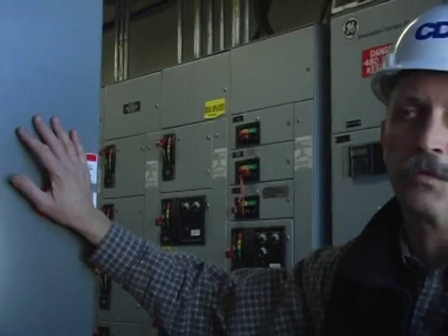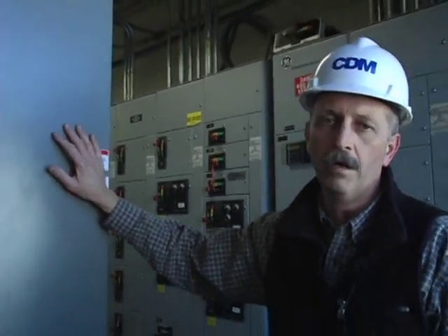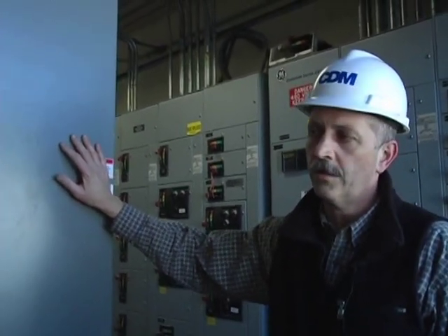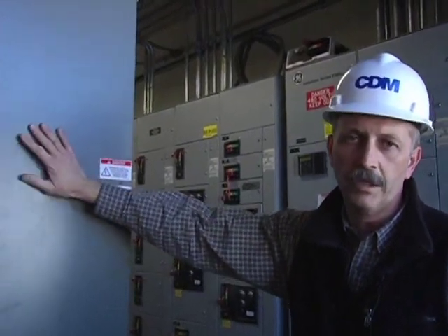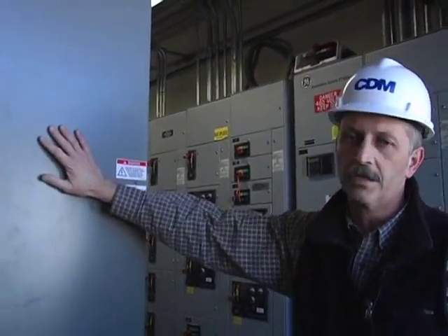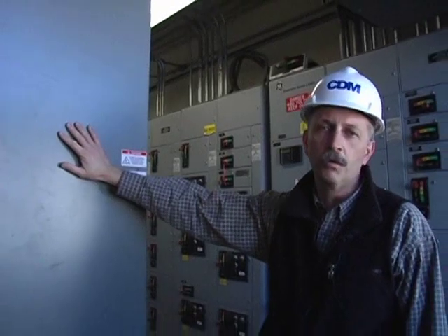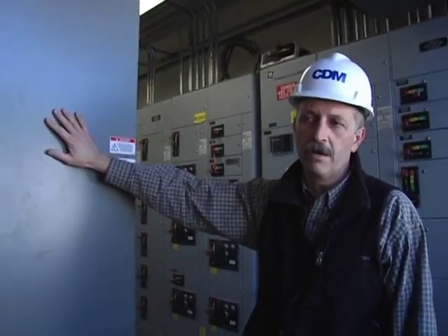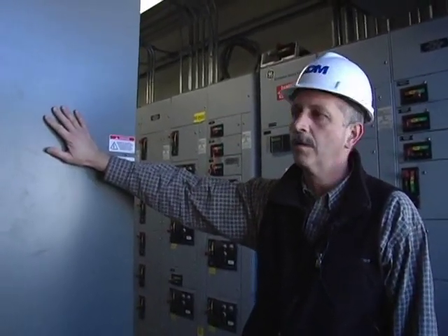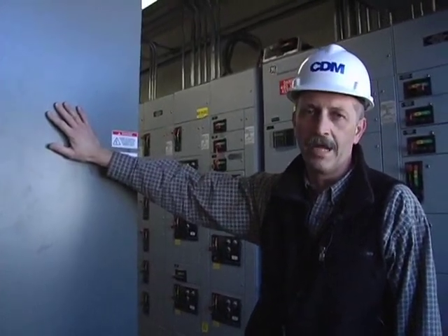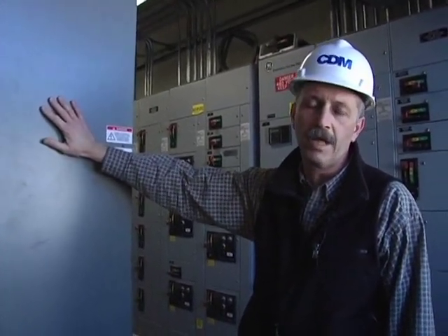Okay, in the electrical room in the East Grit, all of the power feed coming into the building comes into the main substation in the center of the building. This is both utility power as well as the generator power. The automatic transfer switchgear is located within this substation itself, so that if we lose utility power, the generator will sense the loss of power, bring the generator on, and transfer that load to the generator.